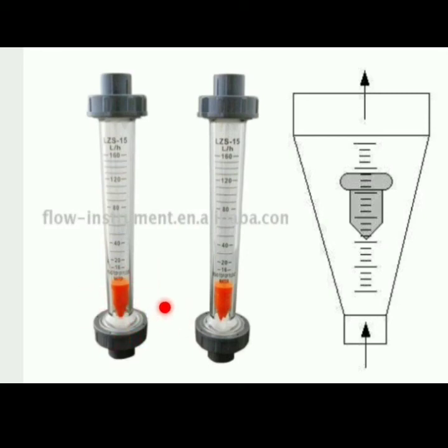And these rotameters are available with electric and electronic transmitters for recording also. Also these floats or plummets of different densities are available, so that a 20-fold range of flow can be measured accurately. Floats may be made of lead. This plummet or float is made from either lead, aluminum, glass or plastic. Then this is all about the construction.